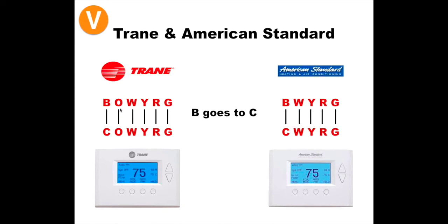The way I do it is O doesn't have any other uses, O is always going to be a reversing valve, especially for our thermostat. So if I see an O, I automatically put it into the O terminal on our thermostat. At that point I have to figure out what the B is doing. Again, the rule is you can't have B and O wired up at the same time, but there are exceptions with Trane. So if I already have O wired up and there's still a B left over, B goes to C, because sometimes Trane American Standard uses B as the 24-volt common wire. Hopefully that helps you remember.